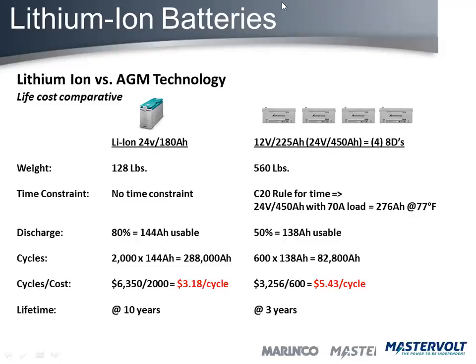The time constraint on the AGM battery bank with a 70 amp load - this is information you can get from the spec sheets from a battery manufacturer. Because of the time constraint of an AGM battery, the capacity is no longer 450 at 70 amp, but 276. We typically discharge those batteries at 50%, so really your usable capacity is 138. With lithium, we just learned there is no time constraint. We have 80% capacity available, which is 144 amp hours. So you almost have the same capacity in this scenario.